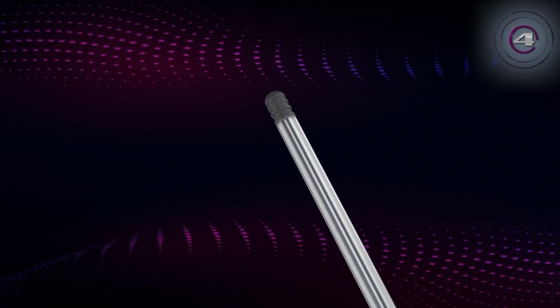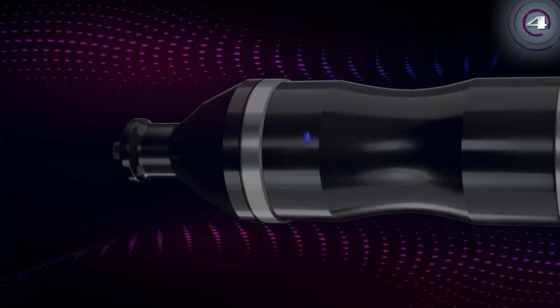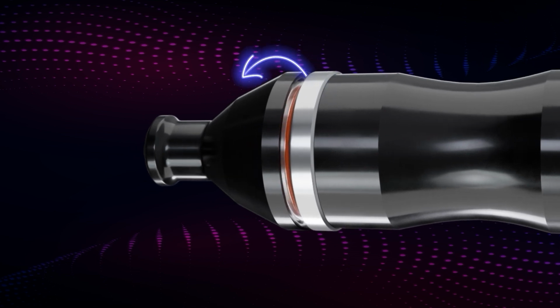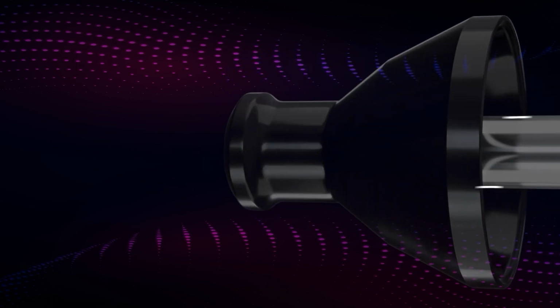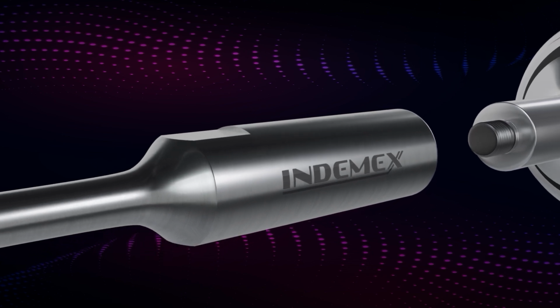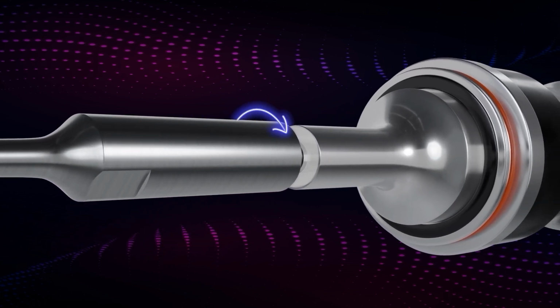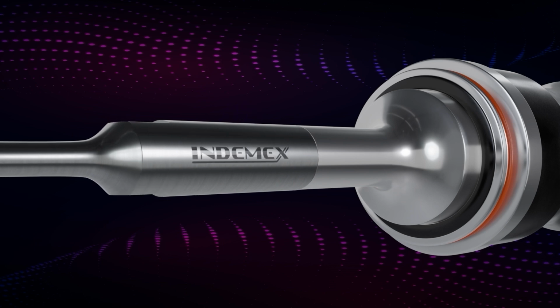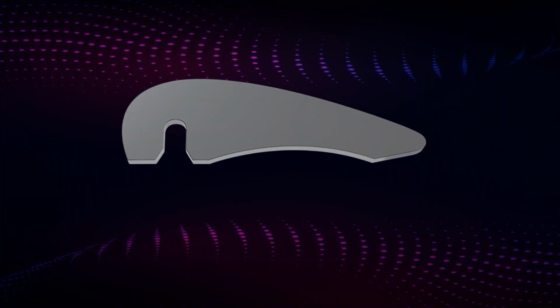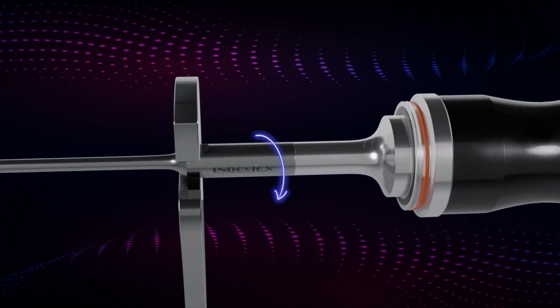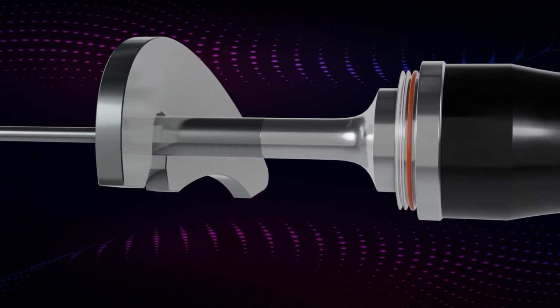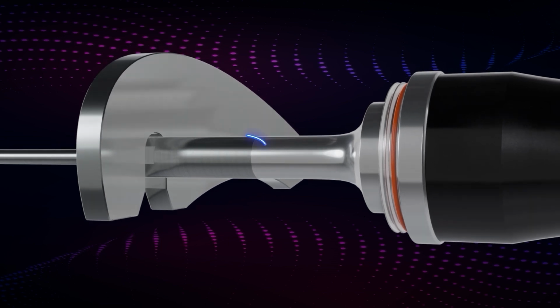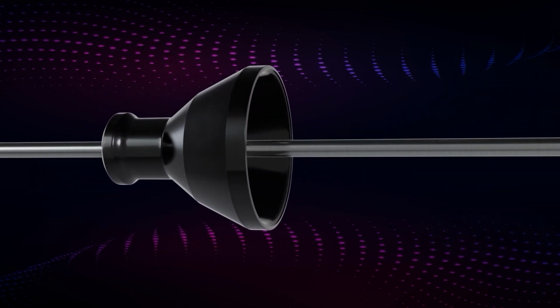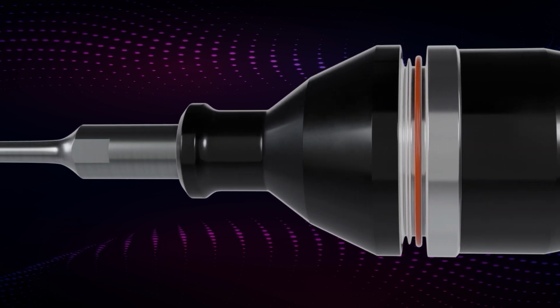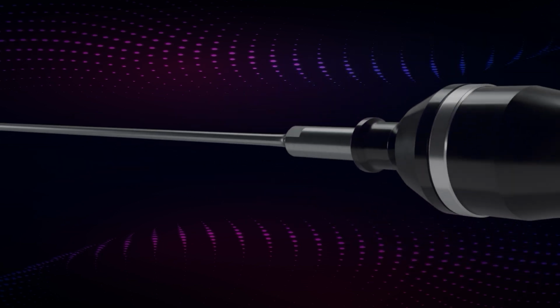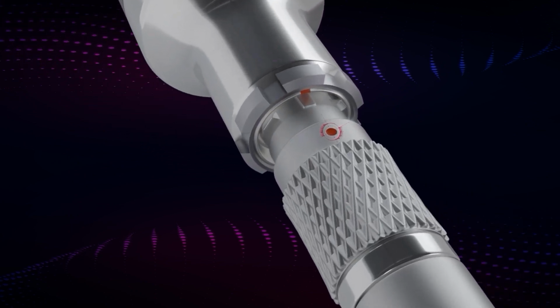Fourth step. To assemble the sonotrode, it will be necessary to remove the handpiece cover nozzle by turning it counterclockwise. Select the sonotrode to be used and insert it into the thread of the handpiece, then twist it clockwise. With a 9mm wrench at the base of the sonotrode, apply torque clockwise until it reaches the stop. Apply little force to tighten it. Place the handpiece cover nozzle back in place by turning it clockwise. Finally, connect the handpiece to the free end of the cable.